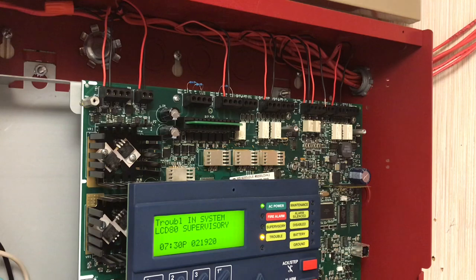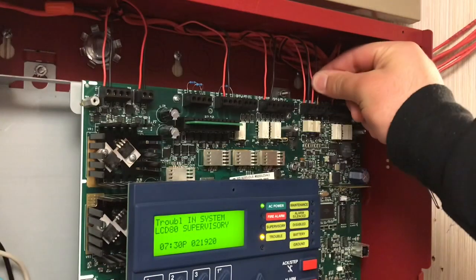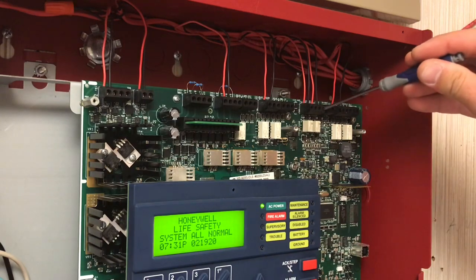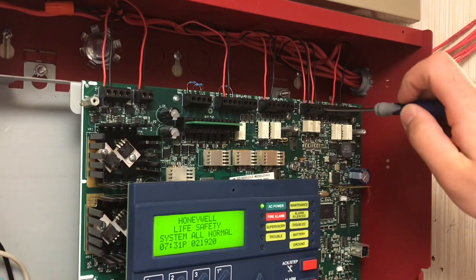I'm going to acknowledge the LCD-80. When it powers up it still has power from the 24 volt non-resettable power, but it lost communication with the fire alarm control panel.